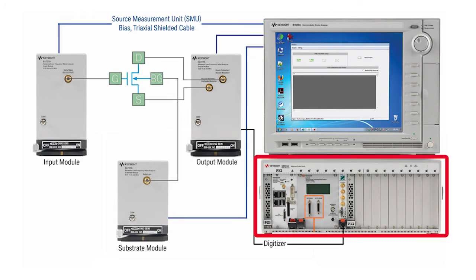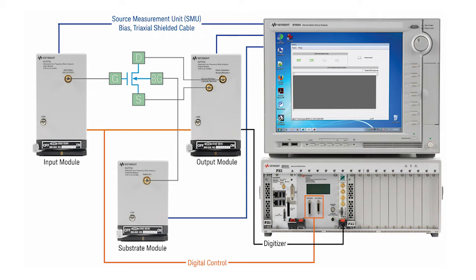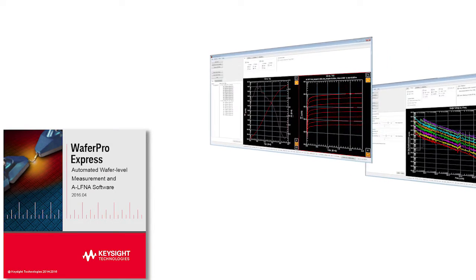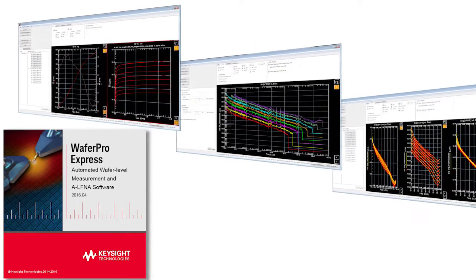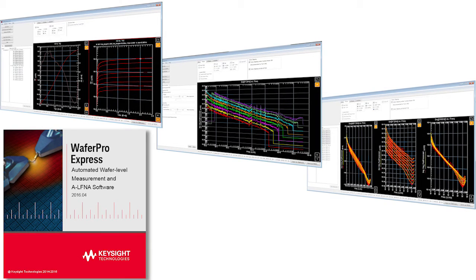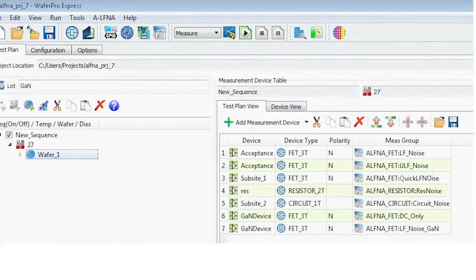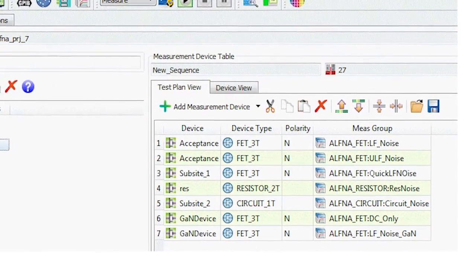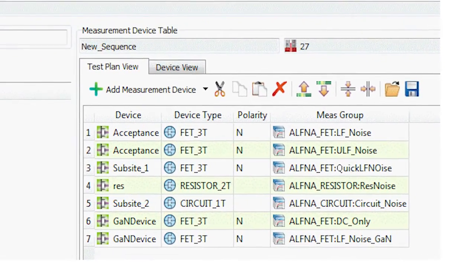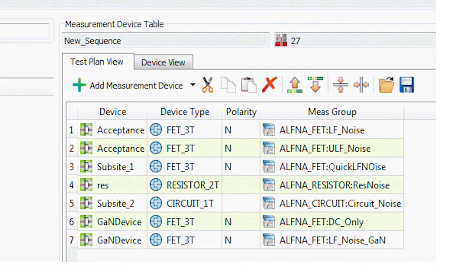It runs from the PXI mainframe and controls all E4727A modules, the wafer prober, and the semiconductor device parameter analyzer. Once the instrument connection is set up, the E4727A software can carry out both DC sweep measurements and noise measurements in the same run without reconfiguring the instrument connection. The user can predefine a set of DC bias as well as noise measurement conditions and set up a measurement sequence that will be executed automatically.